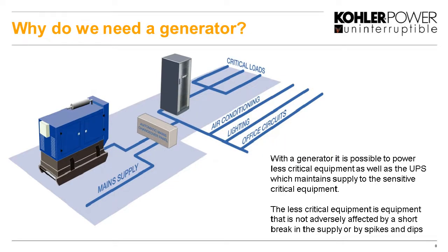With the generator, it's also possible to power less critical equipment. As I said, the UPS will typically provide for just the very critical equipment that cannot have any break or any change in the supply voltage or frequency. That's what the UPS does. But we also have essential equipment that's not so critical to the mains, such as air conditioning, lighting, and other office circuits, as you see here. That is where the generator is very good, because on an outage the generator will be able to supply not only the critical load via the UPS, but also that less critical but still very important load like the air conditioning and lighting, etc.